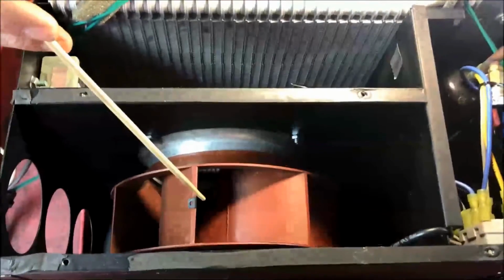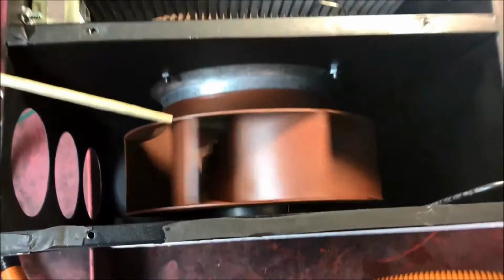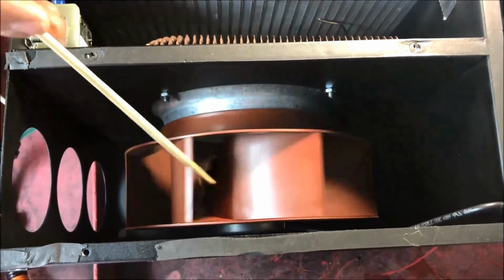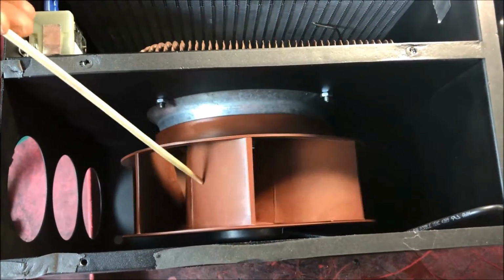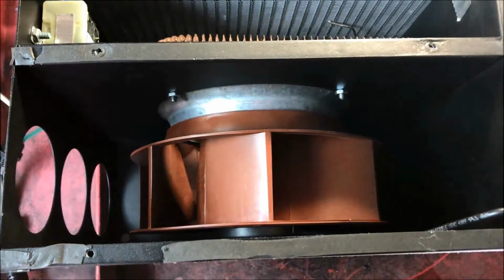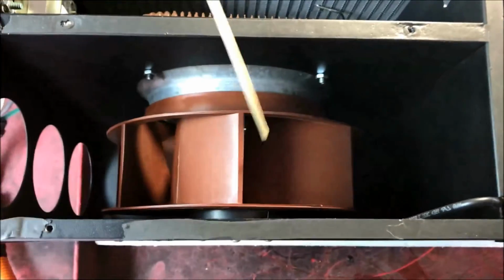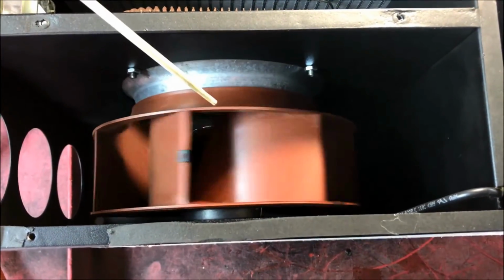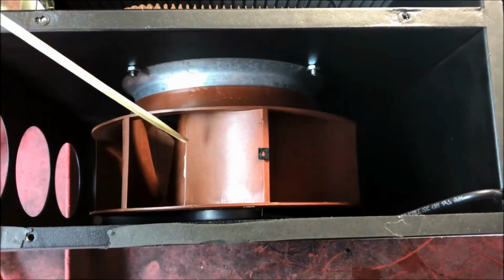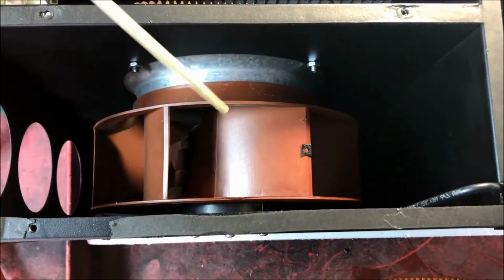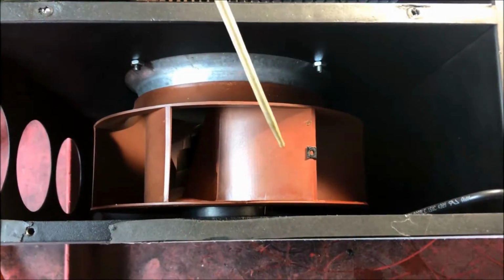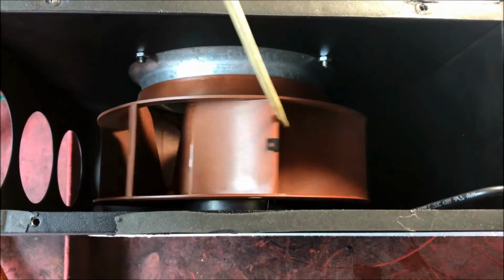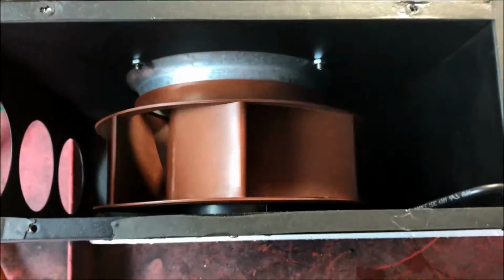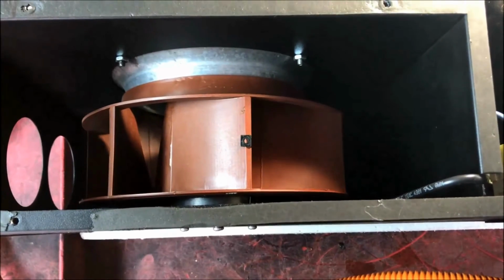Okay, the blower. The blower is a 120 volt AC device. Be careful working on it. It is attached to the circuit board at J20 and J22. It is variable speed. The circuit board increases and decreases the voltage to get the different speeds. The blower has three speeds, but in heat mode, it only has two. It only has low and medium. There is no high speed on heat, so be aware of that. That's a normal condition.